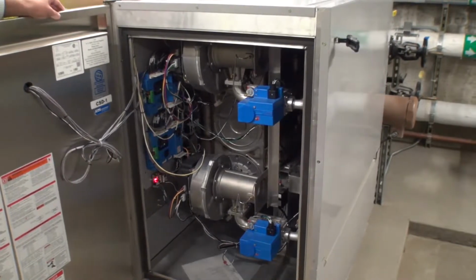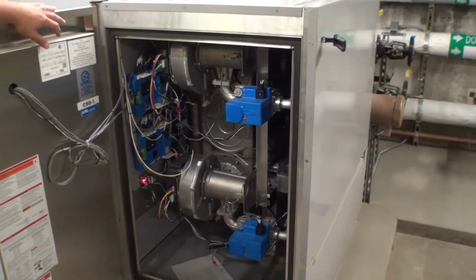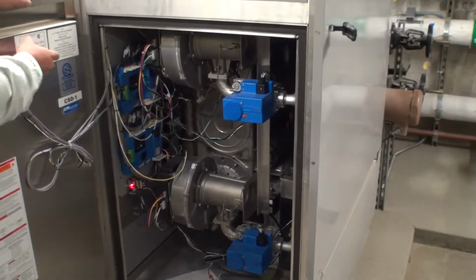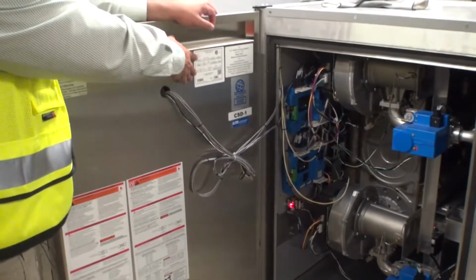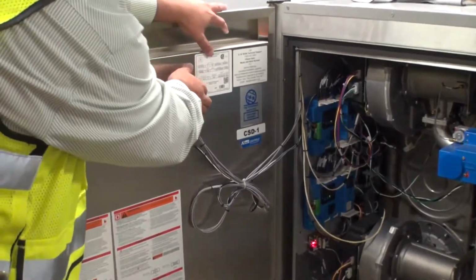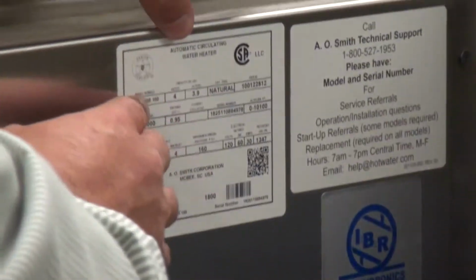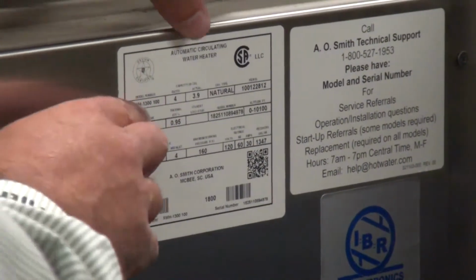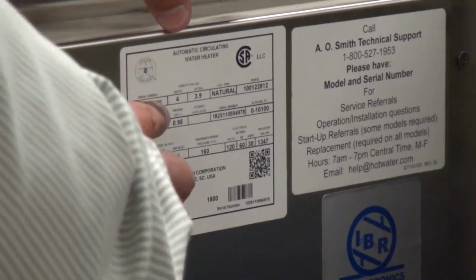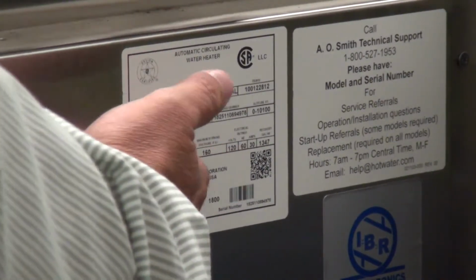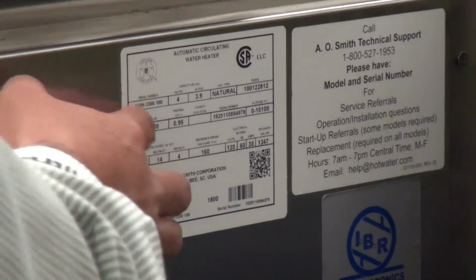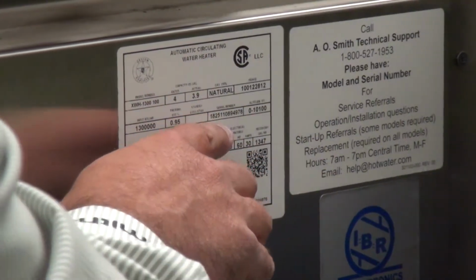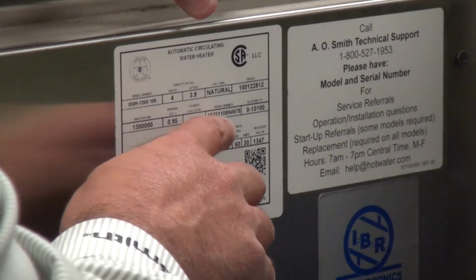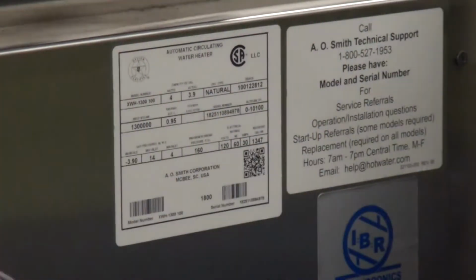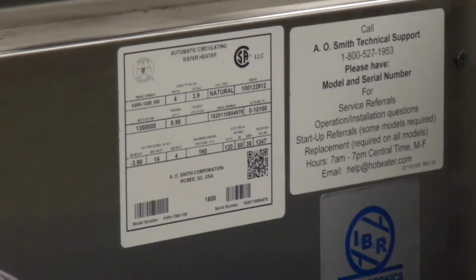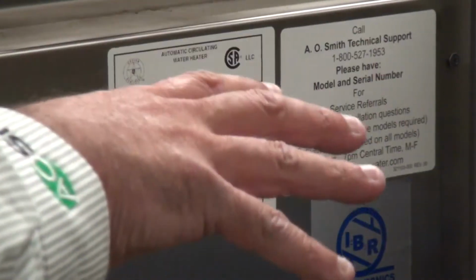When you look at this, a couple things as we open this up to take a peek at, the number one thing to start with is this item ID tag. This item ID tag is going to have what the heater is, so it's going to say an XWH 1300 Series 100. That 100 is the series number, so we'll need to know that information if we call in. It's going to have the serial number, 18251108, yada yada yada. That's going to tell technical service exactly what the build was on this unit.